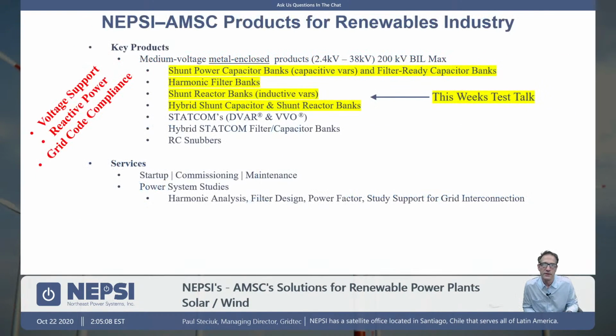So the key products that we're going to be talking about today are shunt power capacitor banks and harmonic filter banks, shunt reactor banks, and more or less when we do shunt reactor banks, we're providing inductive VARs. It means we're taking VARs from the system, more or less dropping the voltage. And then we have hybrid shunt capacitor and shunt reactor banks. So that is what today's Tech Talk is about, those products.